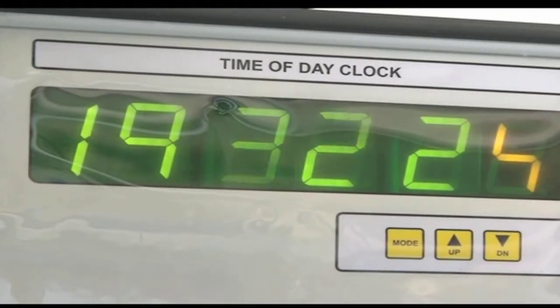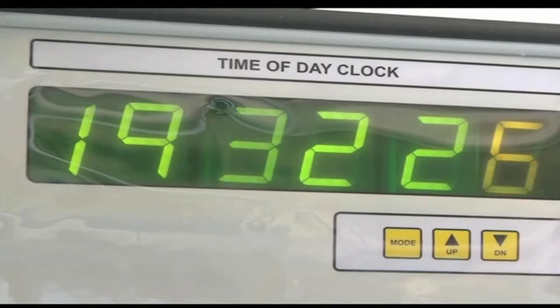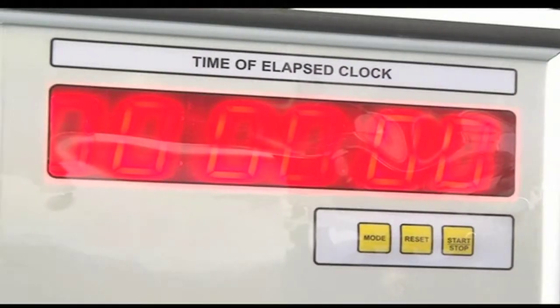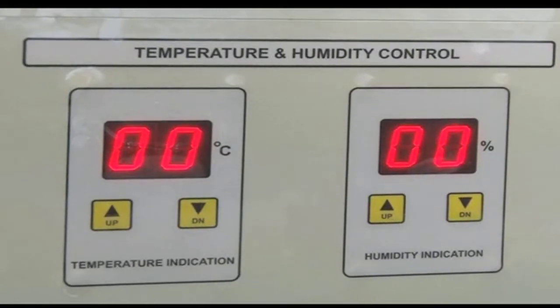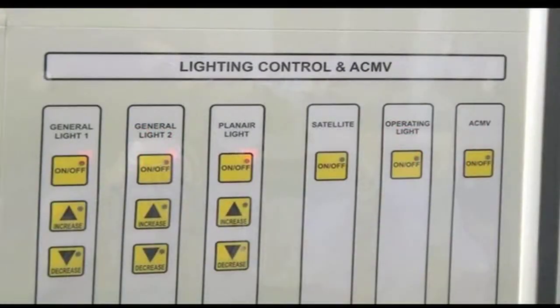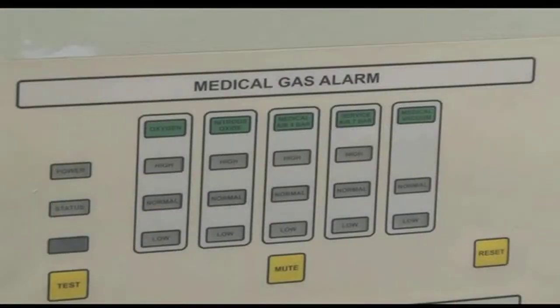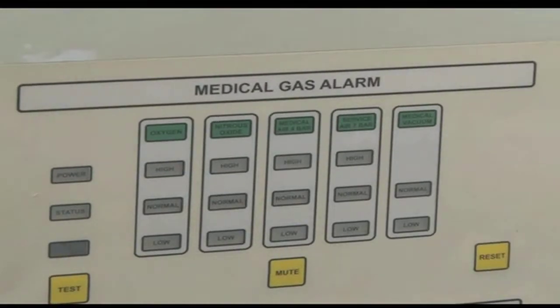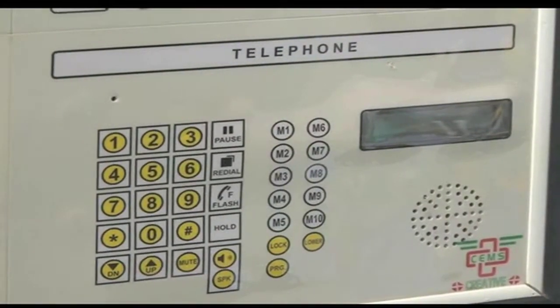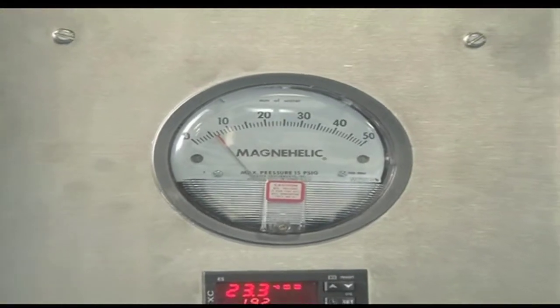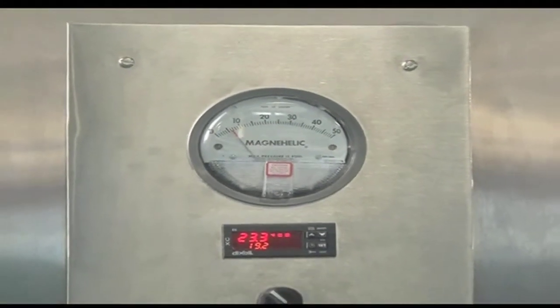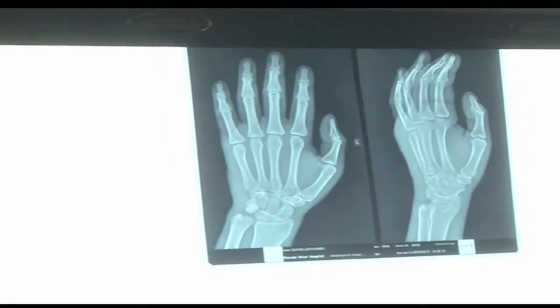The control panel may consist of 9 tiles, namely: time of day clock, elapsed time clock, temperature display or control, lighting control or dimming, medical gas alarm systems, hands-free telephone, HEPA filter status indicator, OT pressure indicator, and X-ray viewer.